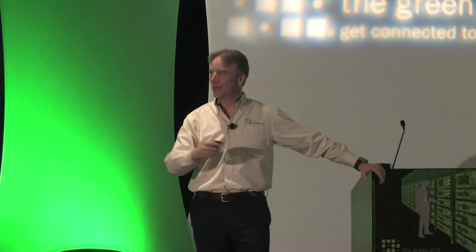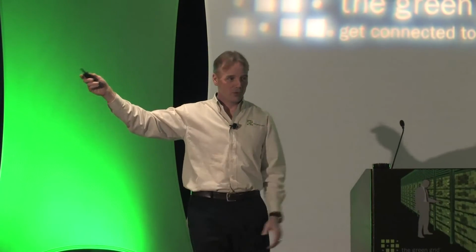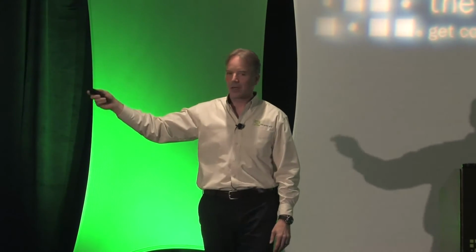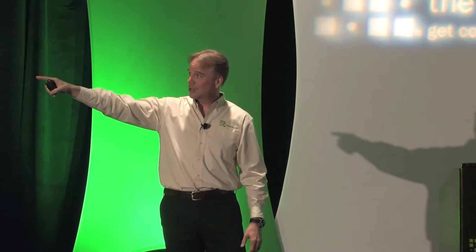Let that sink in too. We just proved that we could get free cooling in a desert with temperatures reaching 119 and above Fahrenheit. Okay? That is aligning the vendors and the warranted equipment actually operating in those environments. The next challenge here, why can't we do that everywhere? Humidity is another big one. Great. Then the challenge should be, why won't we get 100% humidity?